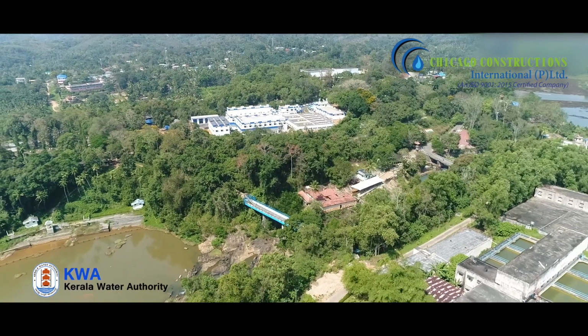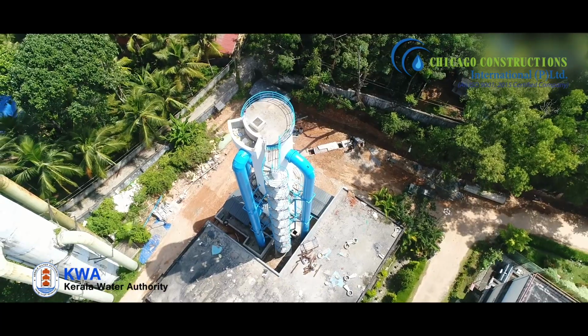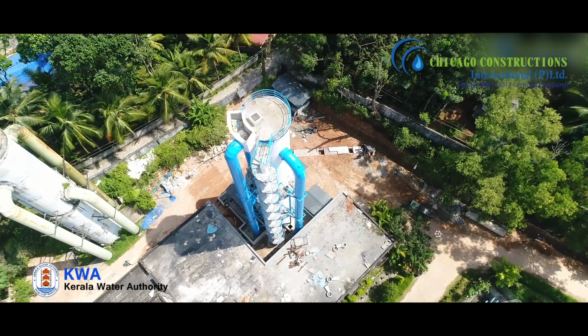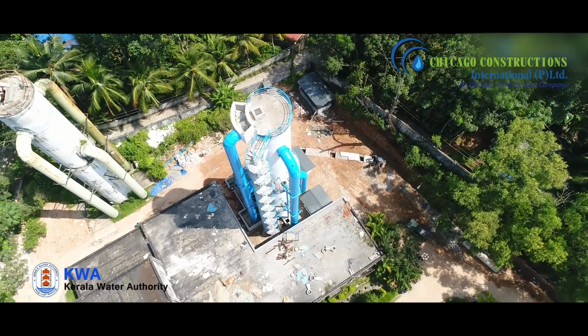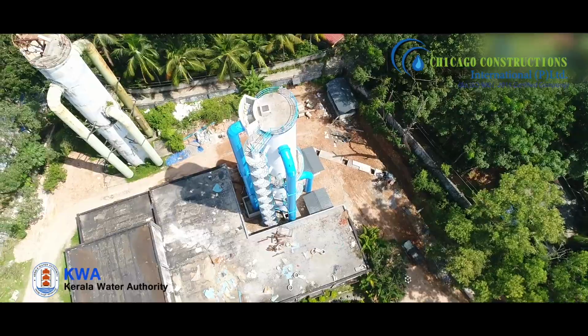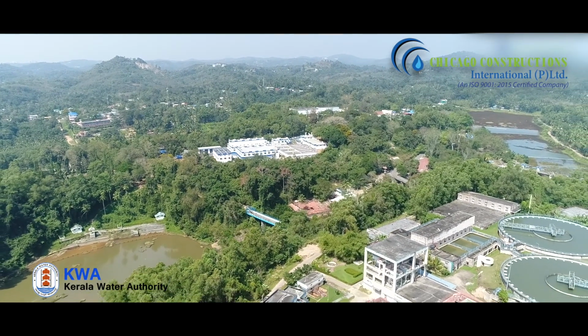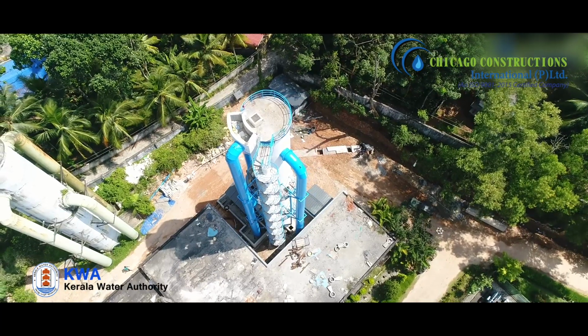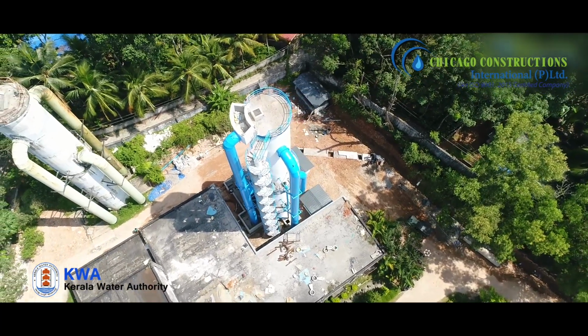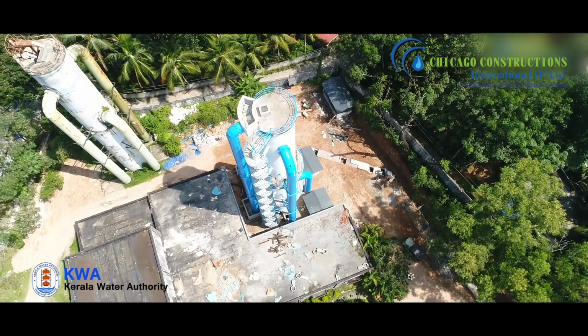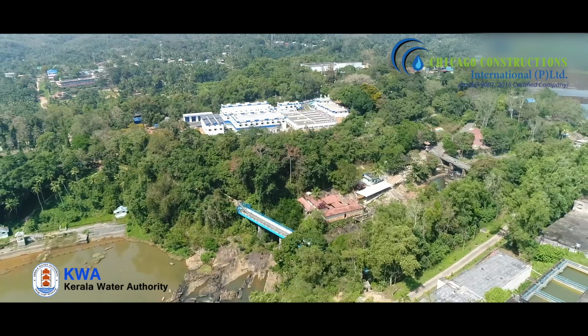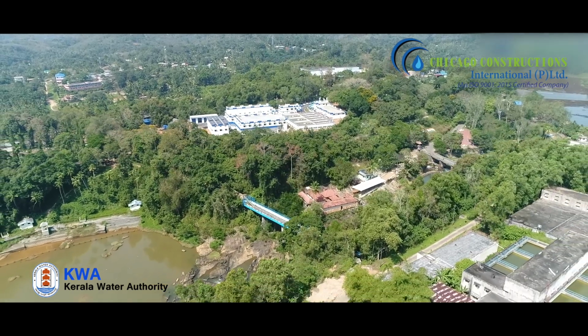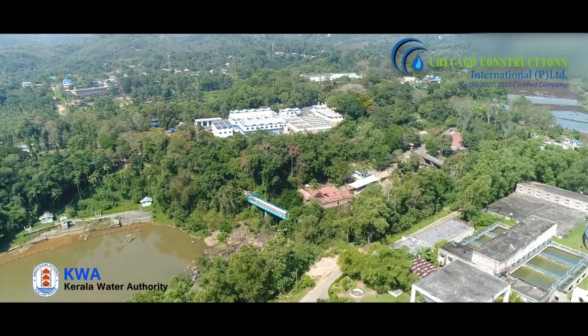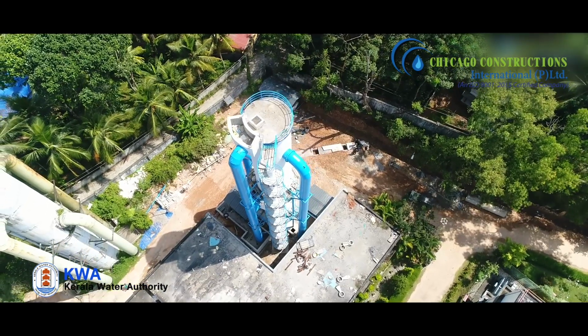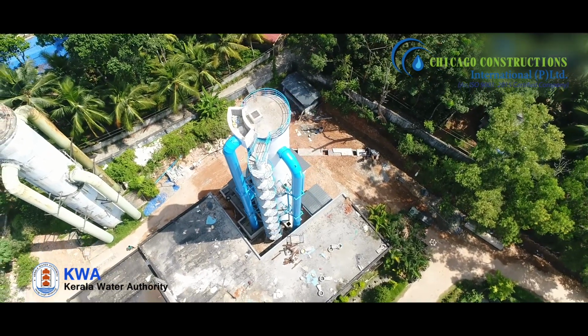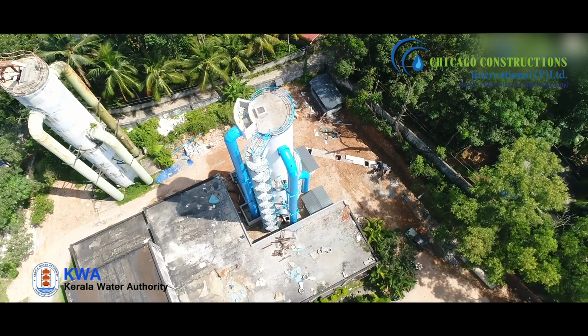The circular break pressure tank of 3.25 meters has 3 chambers with a height of 5.6 meters and another chamber with a height of 7.2 meter above it, which is currently used to supply water to the PTP zone by gravity. Above that, a chamber of 3.25 diameter and 11.5 meter high is used to supply water to the Aruvikkara zone. A break pressure tank is also referred to as a break pressure chamber. In this tank, water is permitted to discharge freely into the atmosphere, which reduces the hydrostatic pressure to 0.